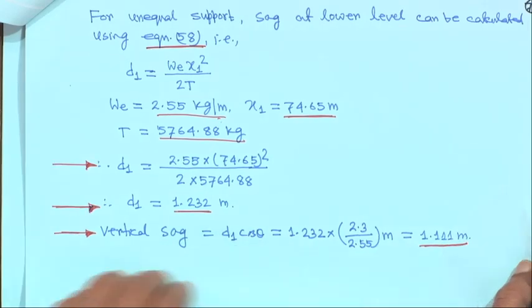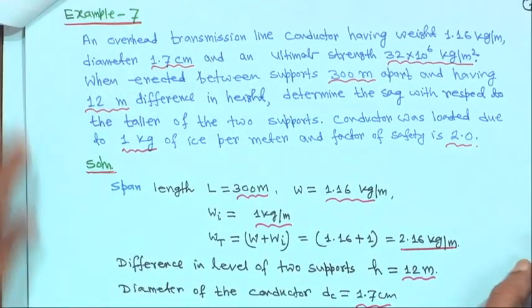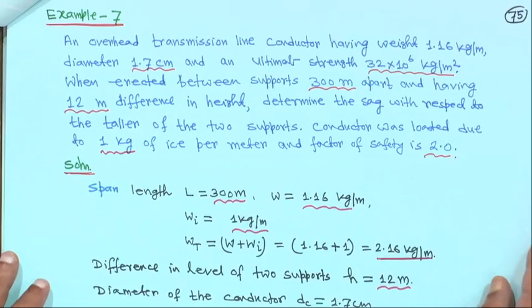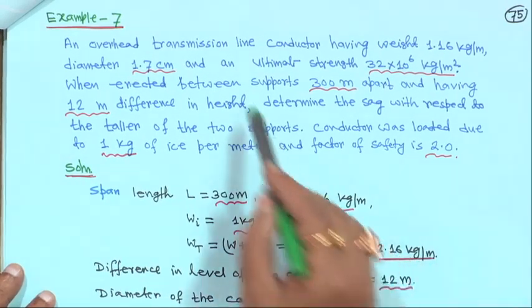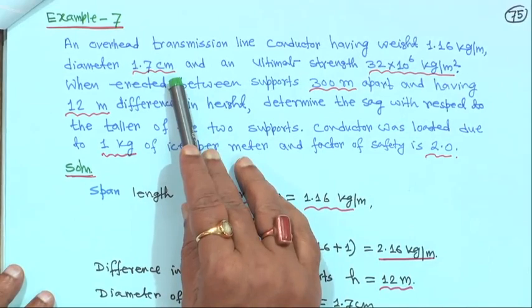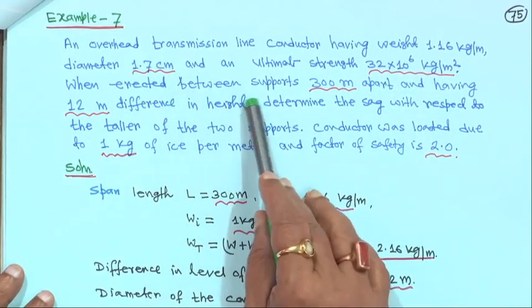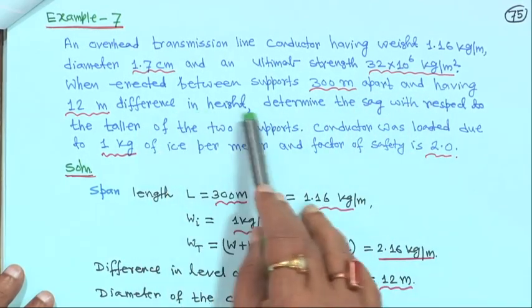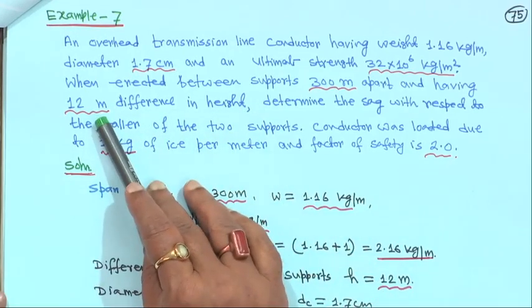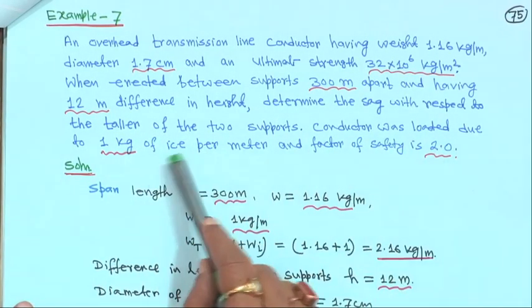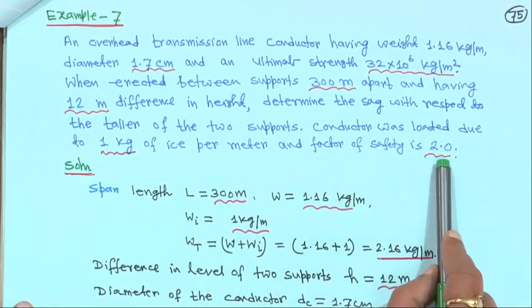Problems are simple; just a little bit of practice is necessary. Now taking another example — example 7. An overhead transmission line conductor has weight 1.16 kg per meter, diameter 1.7 centimeter, and ultimate strength 32 into 10 to the power 6 kg per meter square. When erected between supports 300 meter apart with 12 meter difference in height, determine the sag with respect to the taller of the 2 supports. The conductor is loaded with 1 kg of ice per meter and factor of safety is 2.